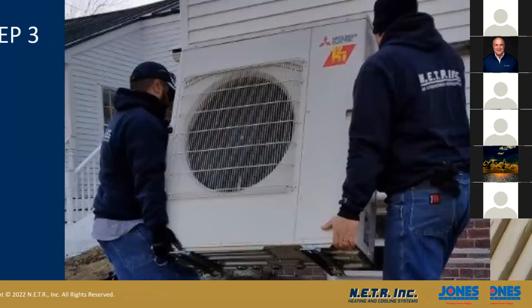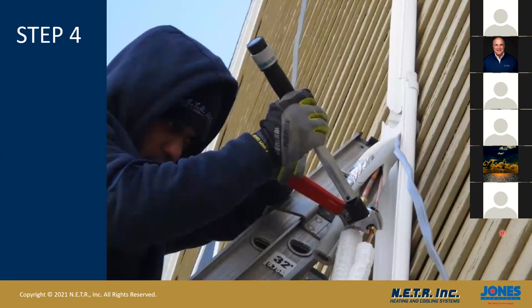The interconnecting piping system, you can see right here of what's going on. You can see the sealant behind here. This hole would also get sealed here. And you can see this technician's using a certain wrench. It looks very big. What he's doing is there's a certain torque on these wrenches that actually tighten these nuts at a certain torque from the manufacturer. A lot of contractors just use two wrenches. They put them together. You have nothing but leaks. So you got to be aware of how things are being put together.